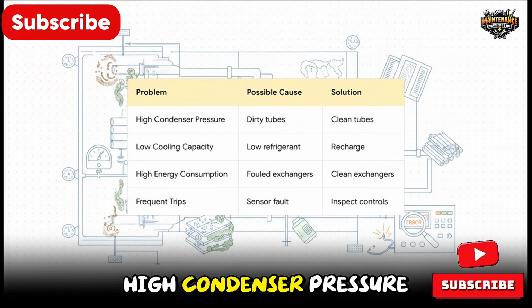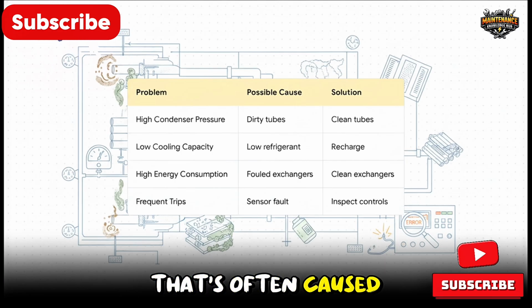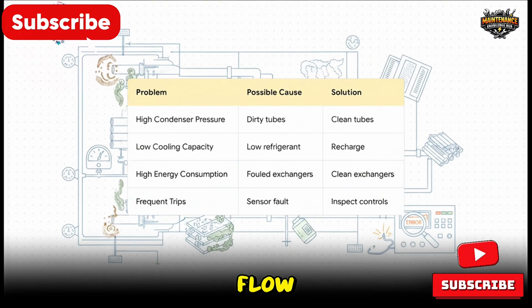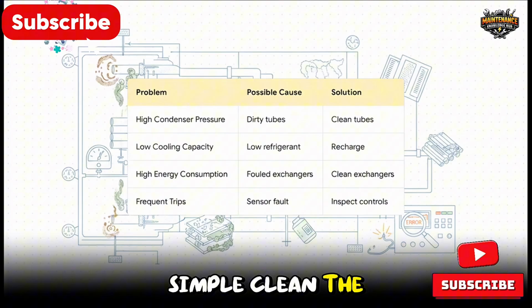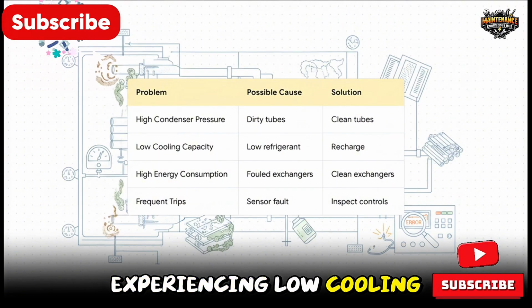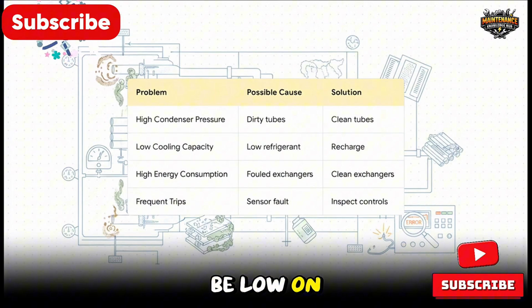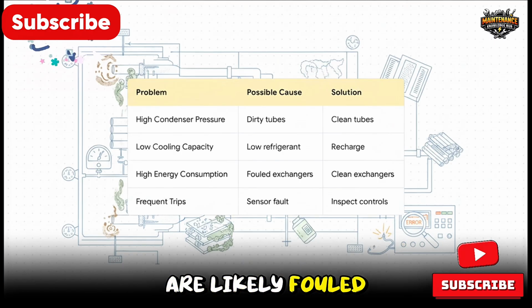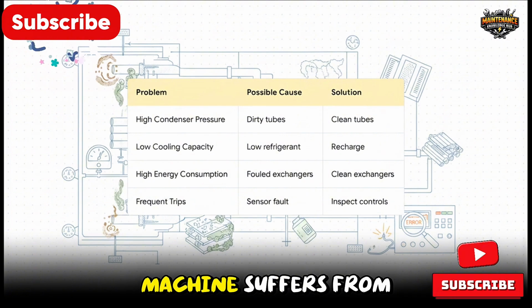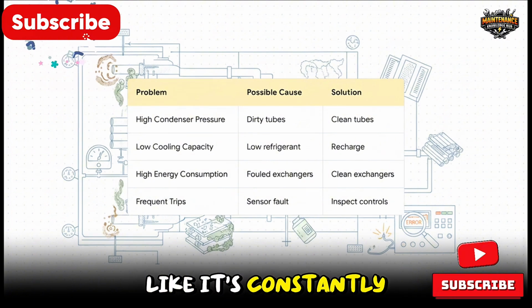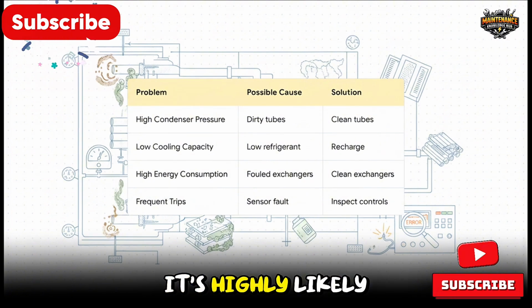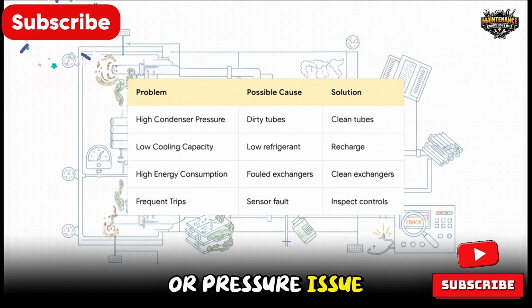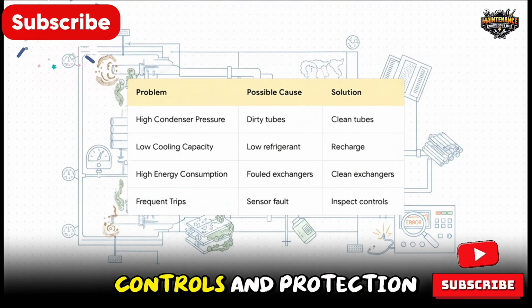Say you have high condenser pressure. Well, that's often caused by dirty tubes or poor water flow. The solution is simple: clean the tubes. Experiencing low cooling capacity? You might just be low on refrigerant and need a recharge. If you notice a sudden spike in high energy consumption, your heat exchangers are likely fouled up and need a deep cleaning. And if the machine suffers from frequent trips, like it's constantly shutting itself down, it's highly likely there is a sensor fault or pressure issue, meaning you need to get in there and inspect the controls and protection devices immediately.